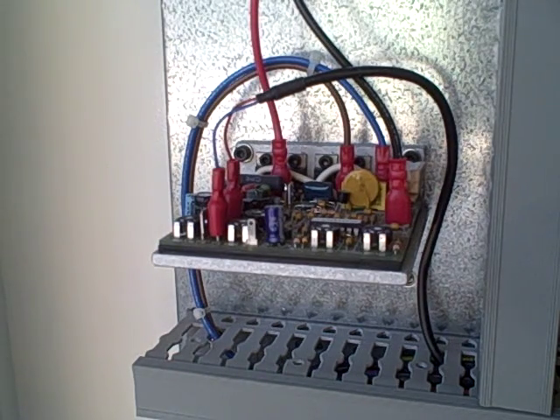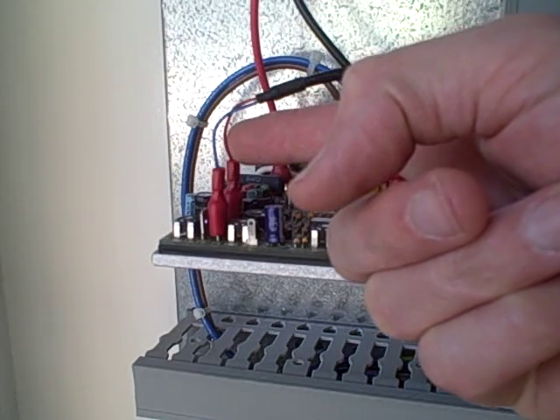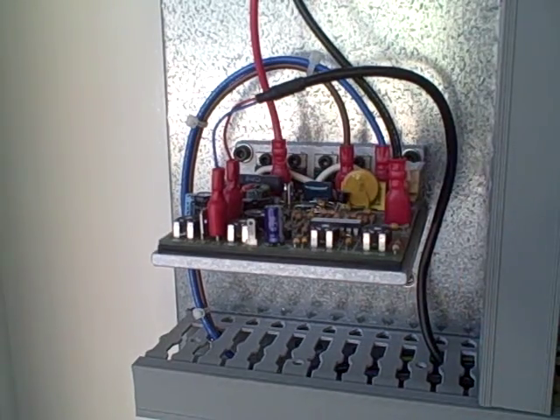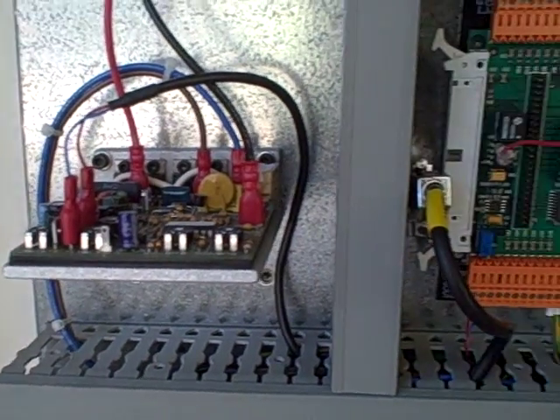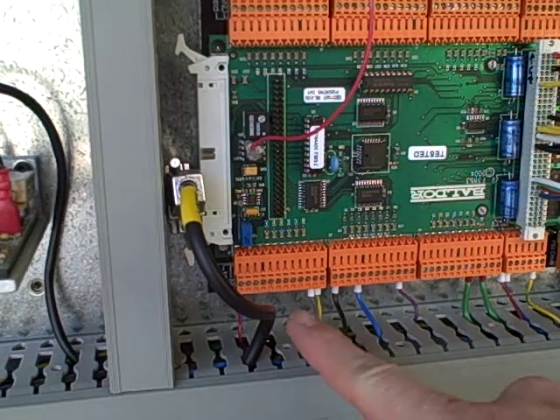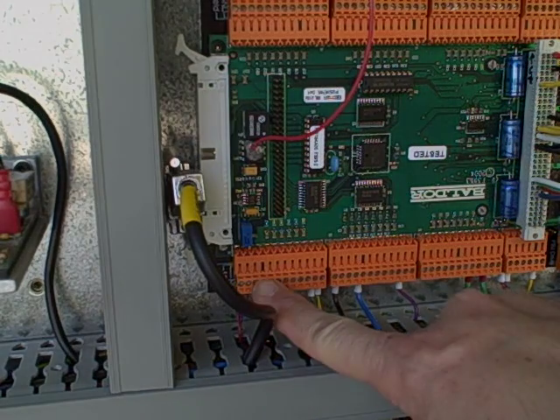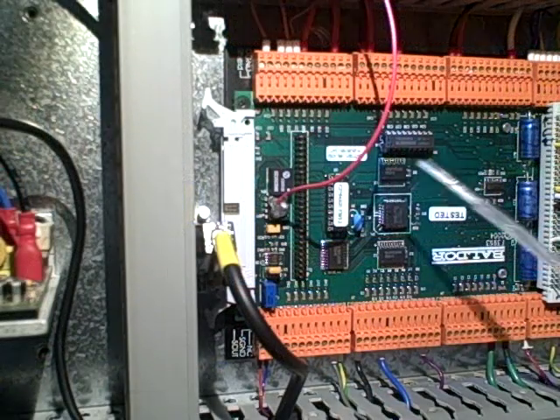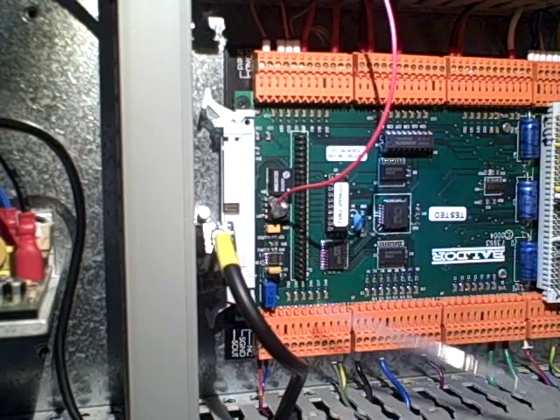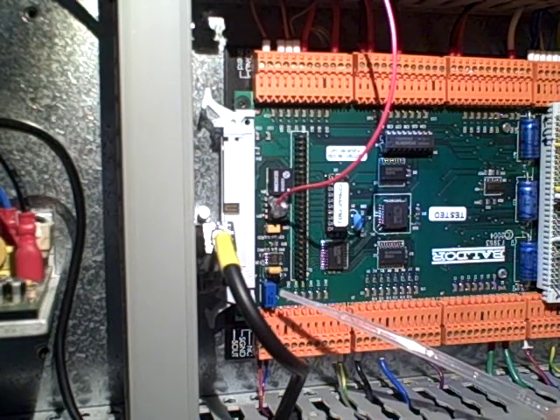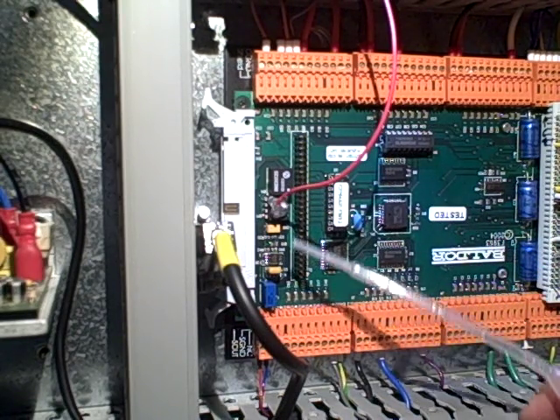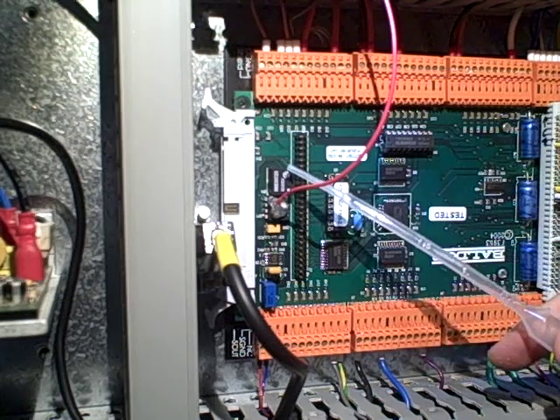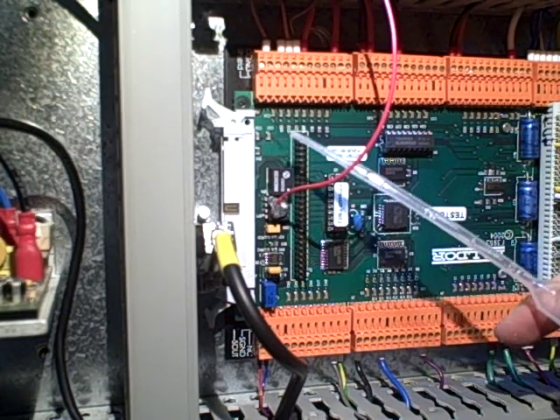The variable speed is controlled via an input here that's a 0 to 10 volt input, and those wires come over from the Baldor Nextmove ST board. So the circuitry over on this side of the board provides that isolated 0 to 10 volt signal off of a 5 volt logic line.